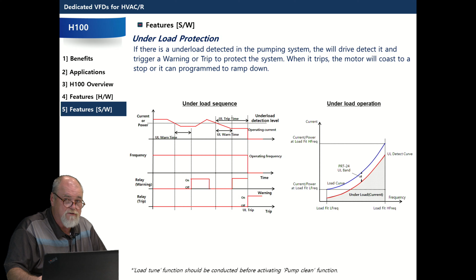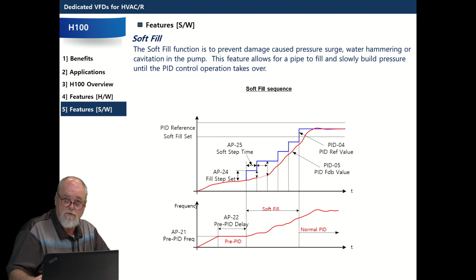I did a pump station in Virginia Beach. Actually, they were pumping from Lake Gaston, which was hundreds of miles away, and in between pump stations you had to fill a 12-foot pipe. So that's a long time to operate wide open, because if you did it strictly on PID loop, the drive would then run wide open. Pipe broken, as I said earlier, we have the ability to determine that the pipe is broken, so thereby we can shut down on an alarm condition.